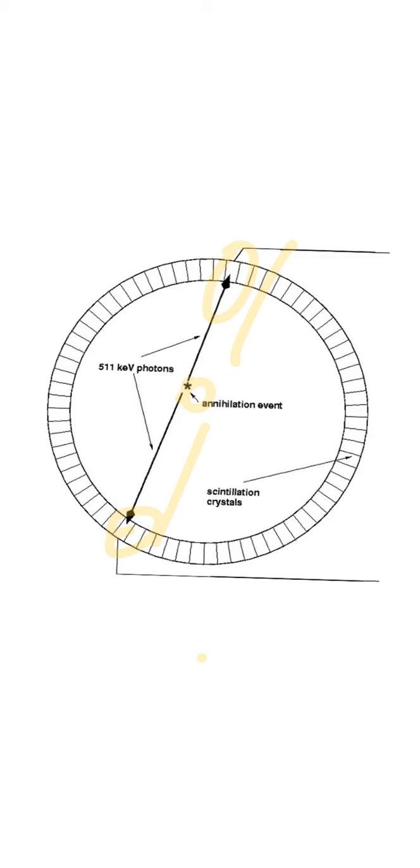So if we have this one here that I'm drawing in green, it can interact also with the detectors across from it within 90 degrees. So this drawing's not too hot, but hopefully that helps you understand how each detector can interact with other detectors that are across from it within 90 degrees.